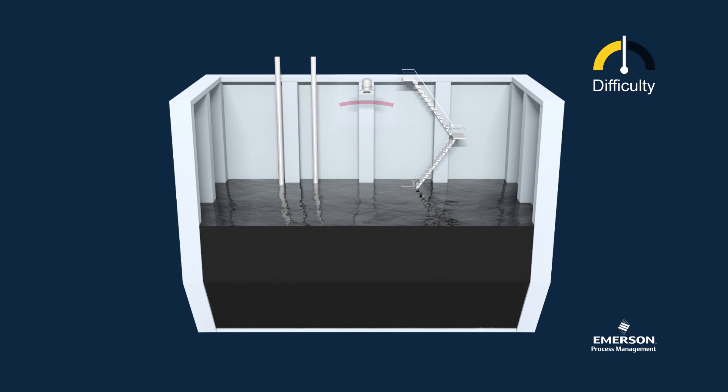Measuring against real cargoes, other than water, is more critical. Loading a liquid like oil means that the measurement becomes more difficult because the oil absorbs much of the radar energy and only a little is reflected.